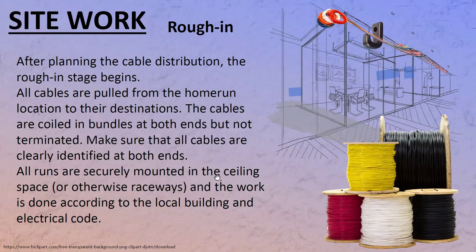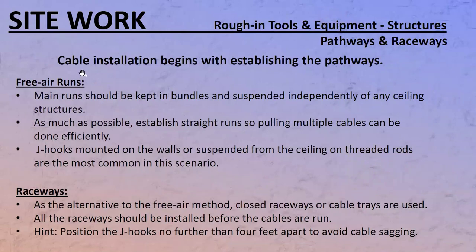For free air runs, main runs should be kept in bundles and suspended independently of any ceiling structures. Previously we used to zip-tie wires to the ceiling rods and run them to location, but we can't do that anymore — it has to do with fire regulations.